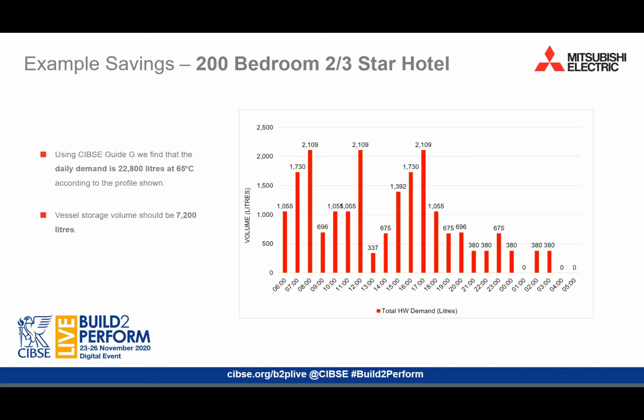Let's consider a typical 2 to 3 star hotel in London with 200 bedrooms. Using the guidance from CIBSE Guide G, we find that the daily demand of the hotel is approximately 22,800 litres of 65-degree water spread across a 24-hour period, as shown in this graph. Here you can see the clear peaks in the morning and evening. CIBSE Guide G also recommends a vessel storage volume of 7,200 litres.